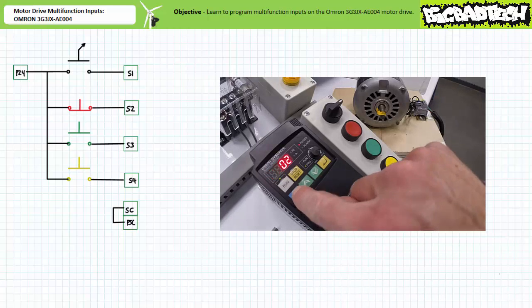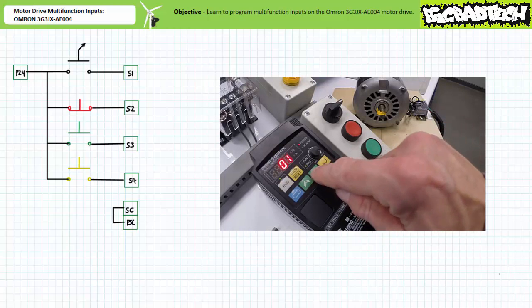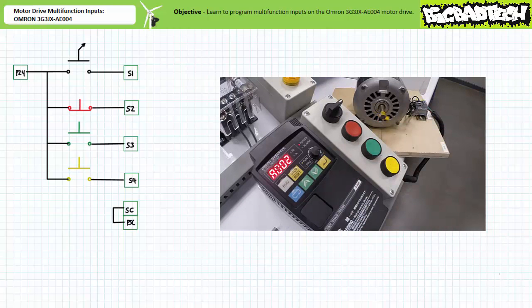As anticipated, it's in the default state of 02 — direct operation via the run and stop/reset button in the digital operator group. Decrement to 01, the multifunction digital input terminal, then select enter to save it. As soon as we press enter, something bad happens — namely, the motor starts spinning in reverse.